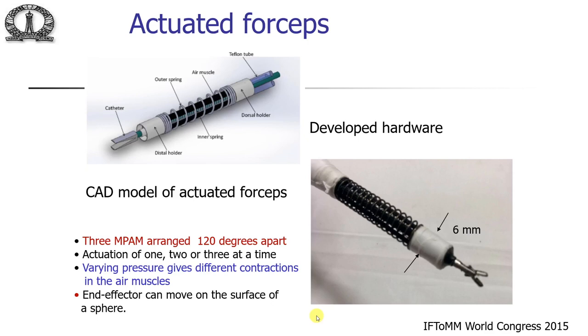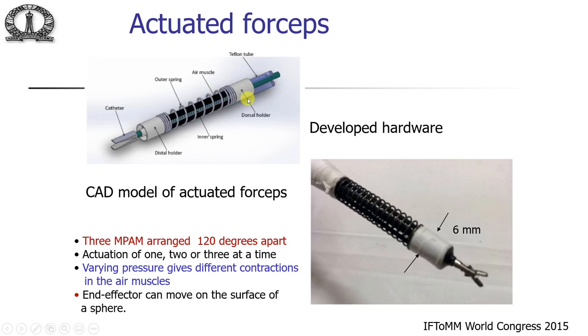Once we have the mathematical model, we use three such tubes arranged 120 degrees apart and made a CAD model of the actuated forcep. There is a holder at each end, and between them are the three artificial muscles. An outer spring helps bring it back when pressure is released, and an inner spring gives stiffness. There is a tube through which air is supplied, and a central channel through which you can send forceps or any other tool.